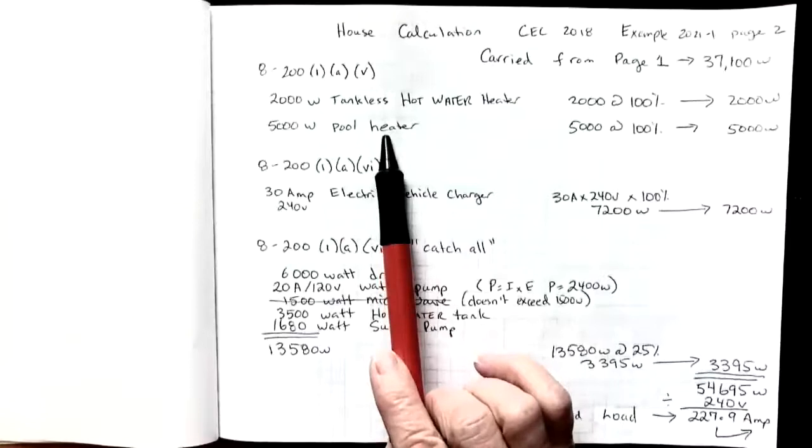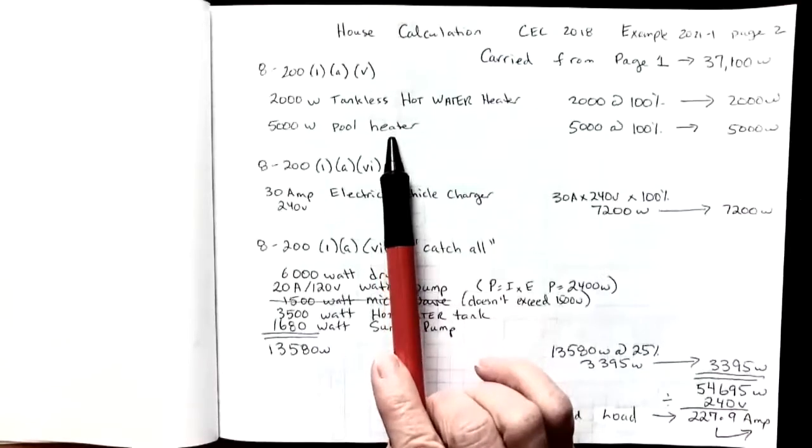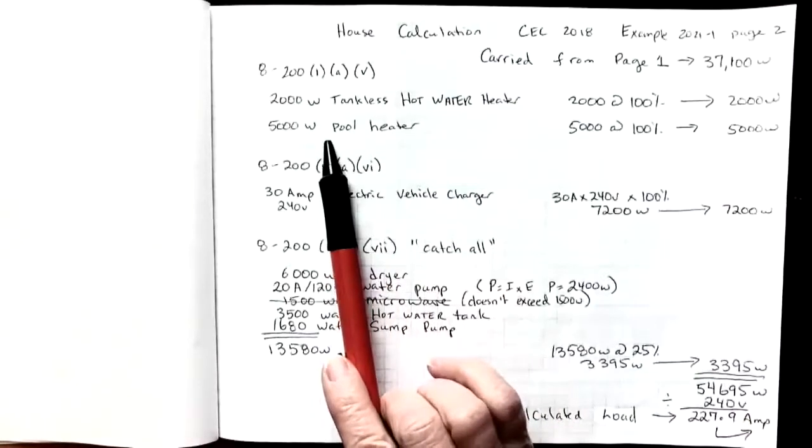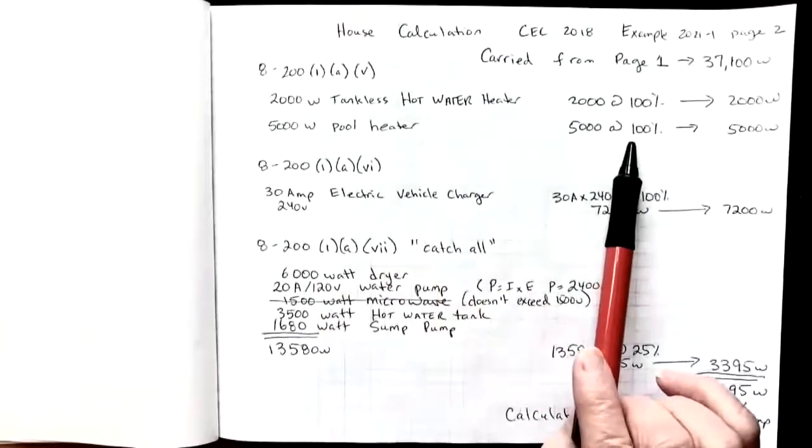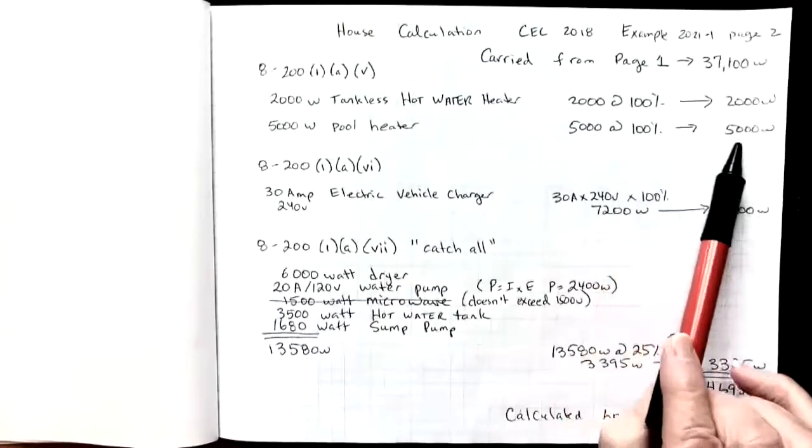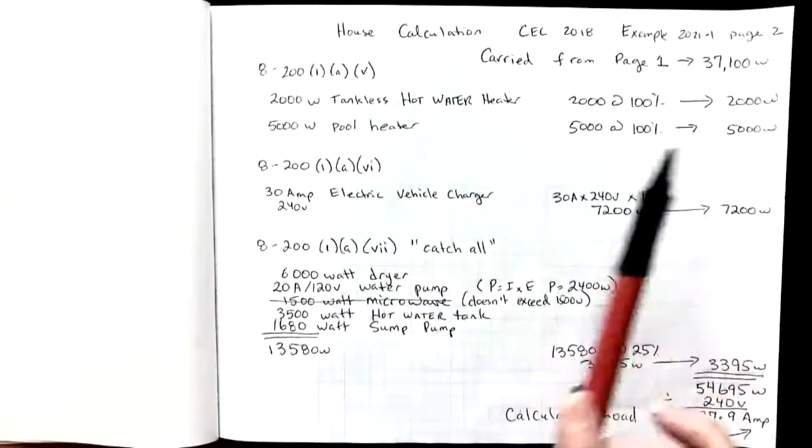This rule also talks about pools and spas and hot tubs. In this example, we had a pool heater, 5,000 watts. That's going to go towards the demand at 100%, so 5,000 watts will be added.